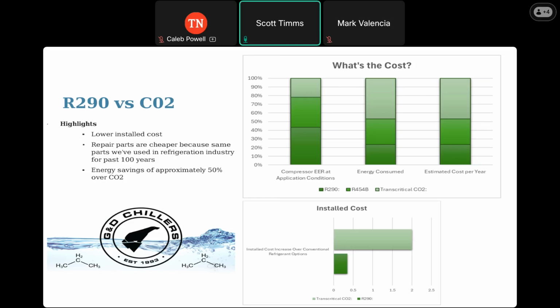And then the other upside to it is CO2. What happens with CO2 is whenever it gets above 82 degrees outside, it goes from being, I'll try not to be too nerdy here, but it goes from being subcritical to being transcritical, at which point you lose about 50% of the capacity, and it requires a lot more operational complexity for it to work. So for that reason, the actual CO2 refrigeration cycle looks quite a bit different than what the standard refrigeration cycle looks like. Whereas propane uses the exact same refrigeration cycle.